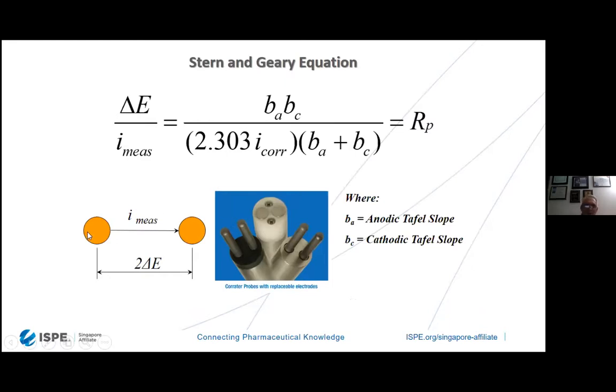And what we're doing is we're doing this eye measurement across these two cathode poles using what's called the Stern-Geary equation from 1957. What this does is it allows us to show what the corrosion rate is and how that corrosion develops over time. That's how we arrive at the Rp, which is the polarization resistance. Point is that we can measure this down to single nanometer levels and even less, but that's how it's measured. Only the probes themselves are sitting in the water. The body of the probe remains outside of the hygienic clamp.